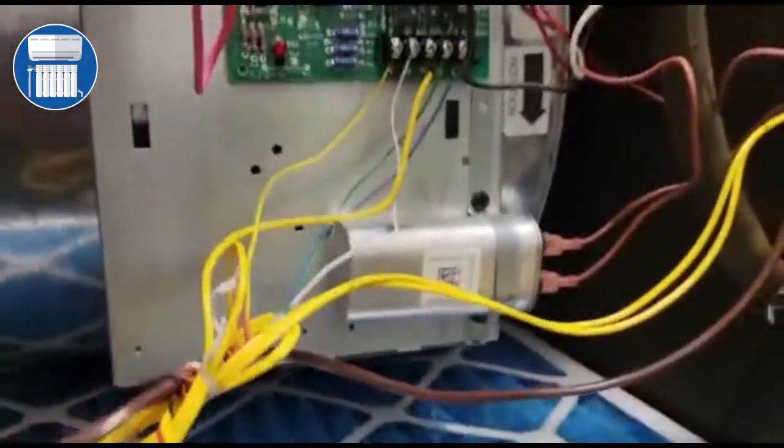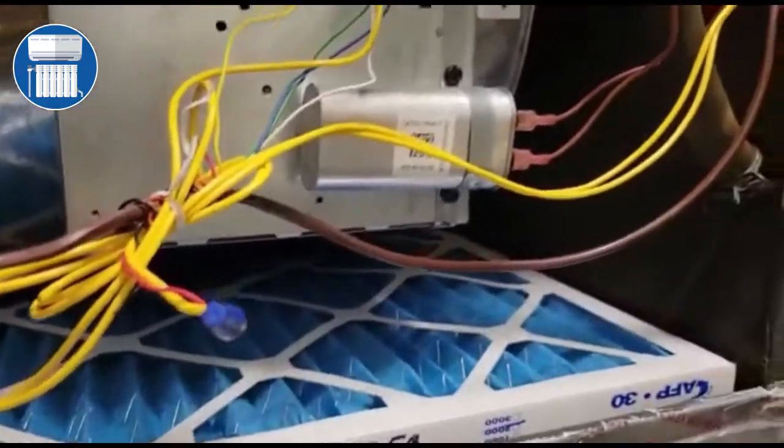And guys, that's how you connect a float switch or a condensate pump. You make sure you have power going around - one end goes to the R terminal here and the other end goes to your red line that you connect from your thermostat.